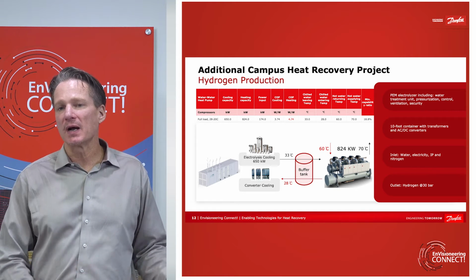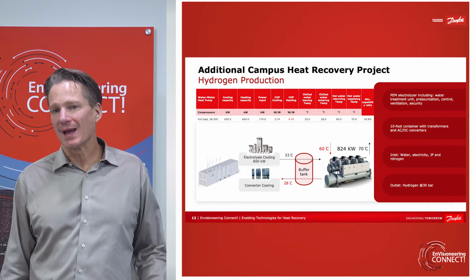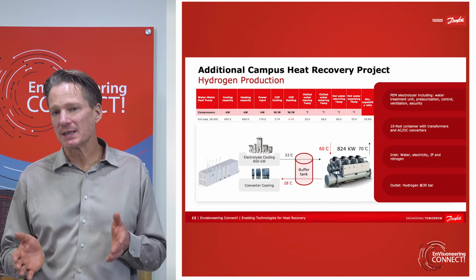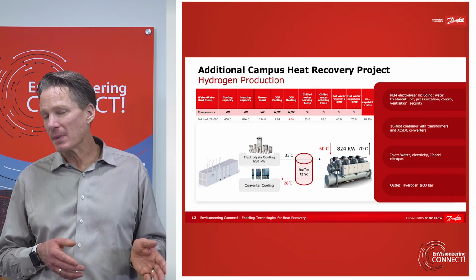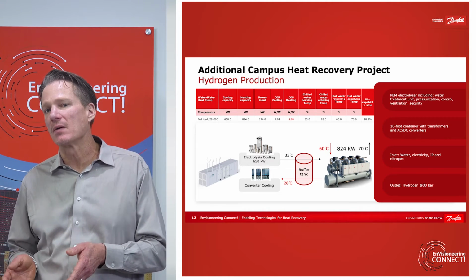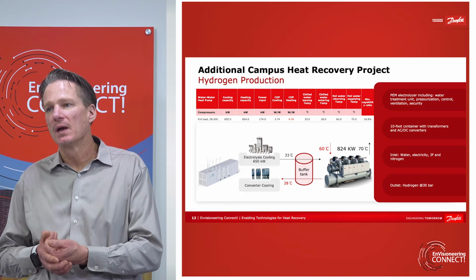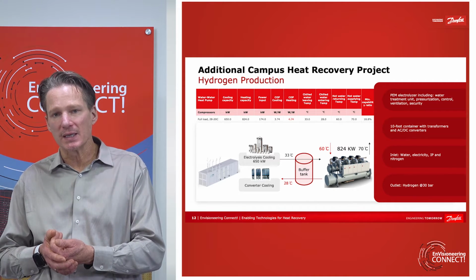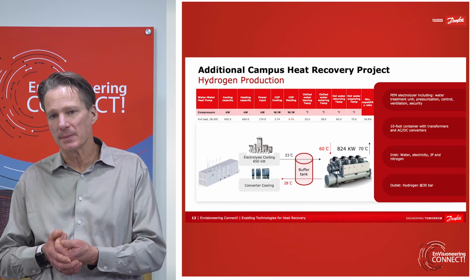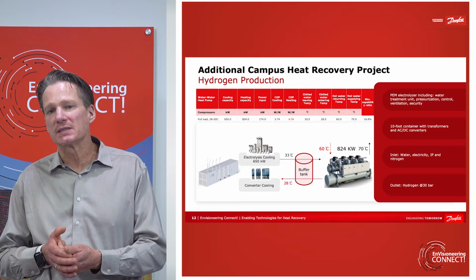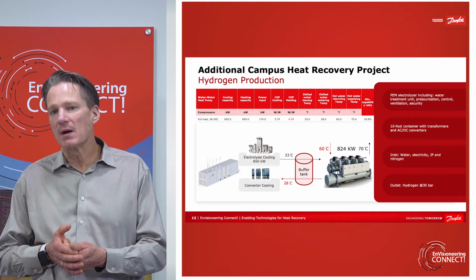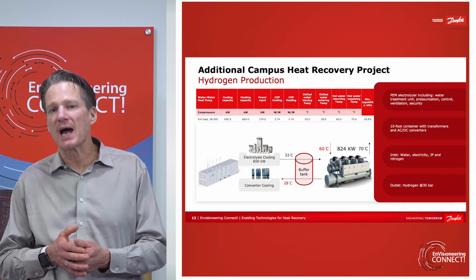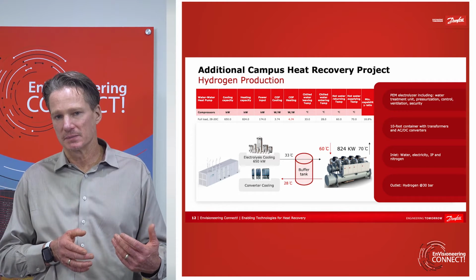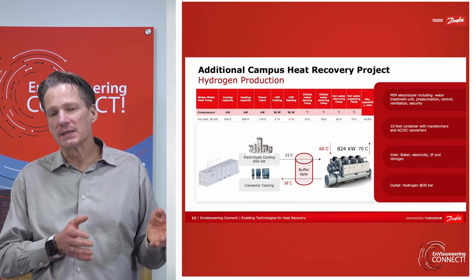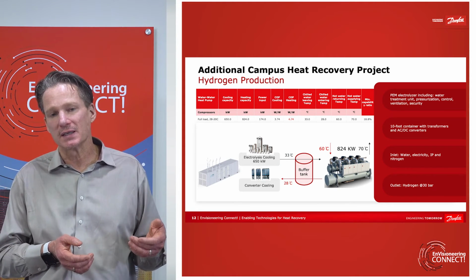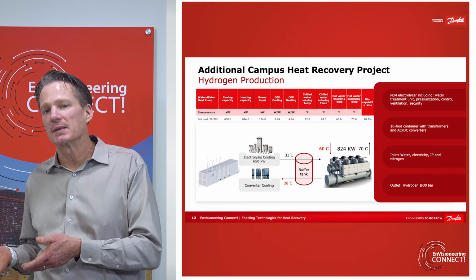So going back to the original driver of the growth of renewables into the power grid and that disconnect of supply and demand, addressing that disconnect comes in the form of storage. But it also comes in the form of backup power on the demand side. So if you're providing backup power at a data center, that's power that the grid doesn't have to provide when those renewable sources aren't available. Those same backup power systems are also transitioning to the point now where they're starting to experiment with the integration of hydrogen production into those power systems. How this takes form is the electrolysis of water splitting out the hydrogen and oxygen, and then the hydrogen going to a fuel cell to generate the power.